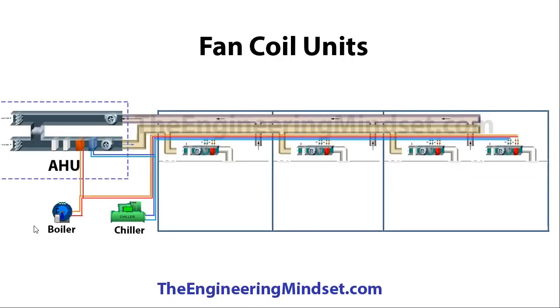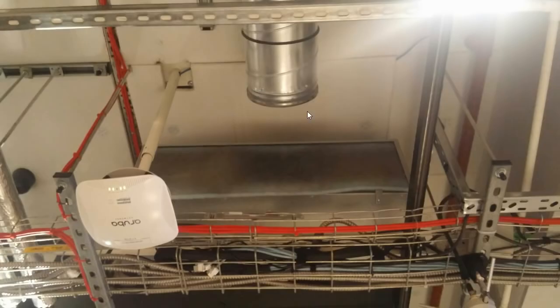Looking at a schematic of how fan coil units work: the main AHU supplies air down through ducts to each room. Not all fan coil units will have a fresh air duct directly connected to them, but each room will have a fresh air connection since there is a requirement for each room to have a certain amount of fresh air per hour. The fresh air duct is not directly joined to the FCU inlet — there's a gap — and the filter can be removed or slid out and cleaned or replaced.